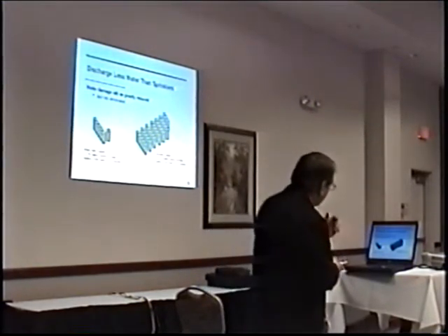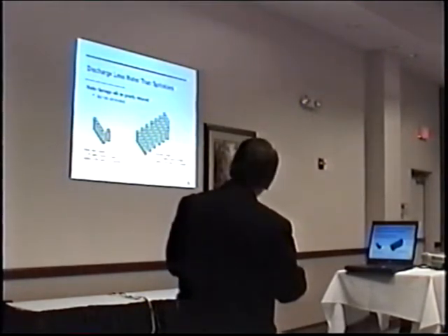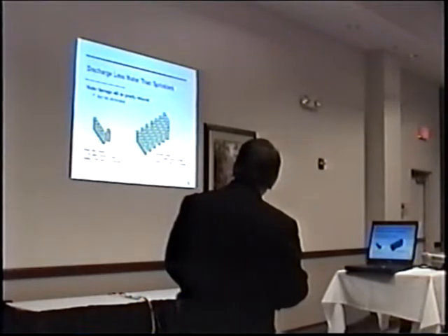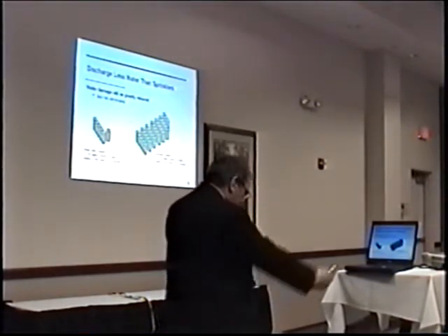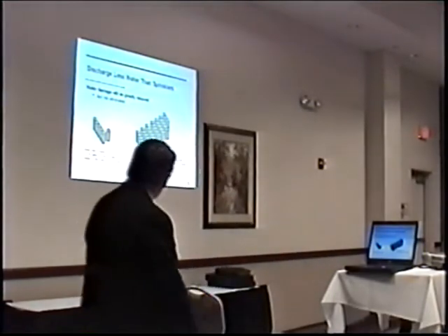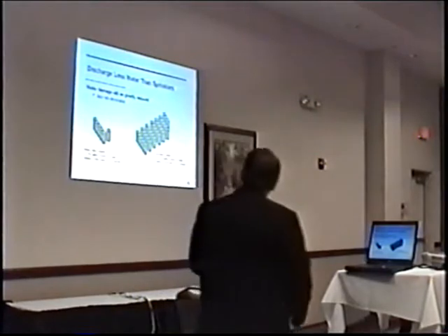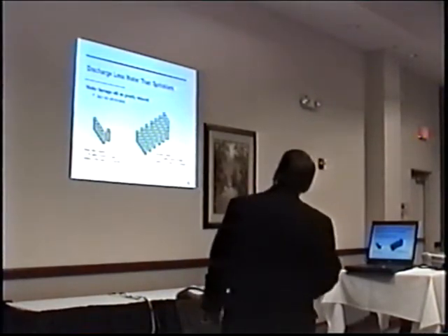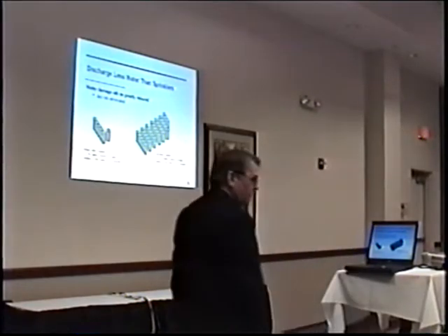And we can see that the sprinkler system would be discharging, at a 15-minute discharge, about 33 55-gallon drums of water. So you imagine a big 55-gallon drum of water, and you tip that over, and you would have an awful lot of water in the rare book vault. While the water mist system took about 6 55-gallon drums of water.